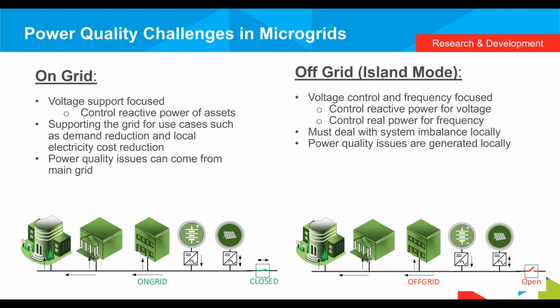Now, when the microgrid or the smart homes is in island mode, that is, off-grid and disconnected from the grid, the primary function of the microgrid is to form the grid, that is, to control the voltage and control the frequency within the required tolerance. To control the frequency, the microgrid has to be able to provide real power, and it should be able to provide reactive power in order to control the voltage.